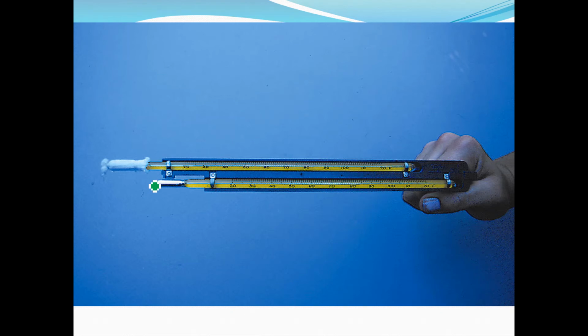Well, what actually happens is, depending on how moist the atmosphere is, a certain amount of water will evaporate off this wick. If the atmosphere is really, really moist, just like when your body sweats and it's really humid outside, the sweat can't evaporate, the moisture won't be able to evaporate off this wick. Therefore, the temperature will not decline much. And the difference between the wet bulb and the dry bulb is very, very small. When this happens, relative humidity is really high. Why? Because the air is close to saturation, water can't evaporate off the wick, so the difference between the wet bulb and the dry bulb is really small.